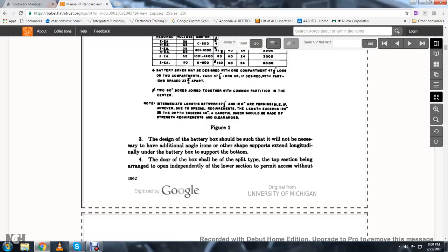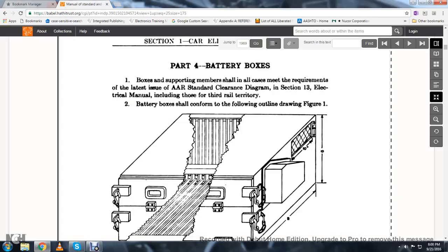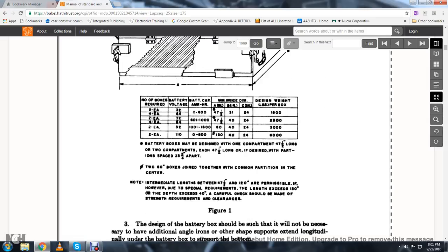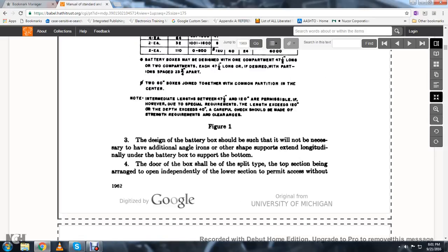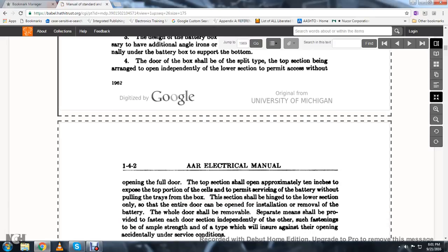The design of the battery box should be such that it is not necessary to have additional angle irons or other shaped supports extending longitudinally under the battery box to support the bottom. The door of the box shall be split type, the top section being arranged to open independently of the lower section to permit access without opening the full door.